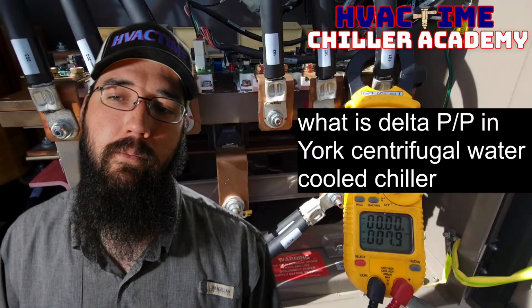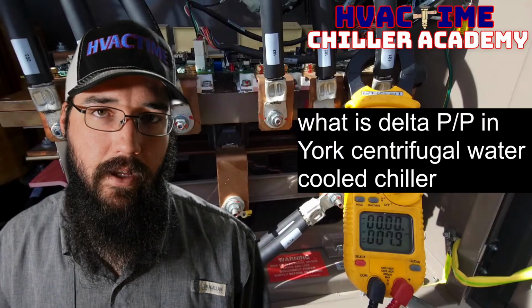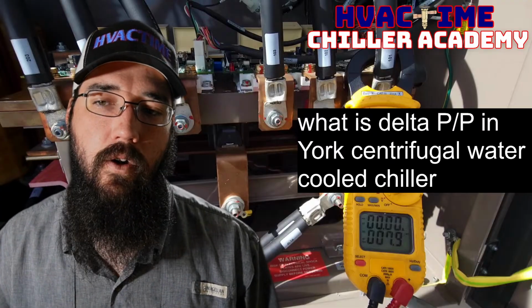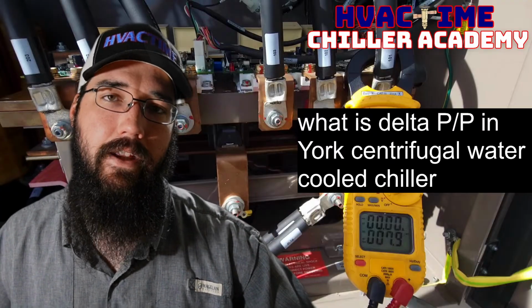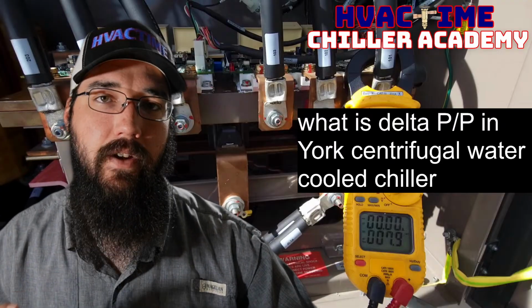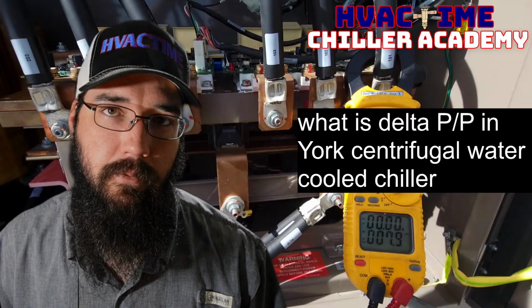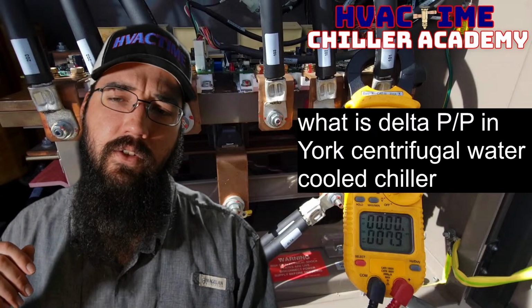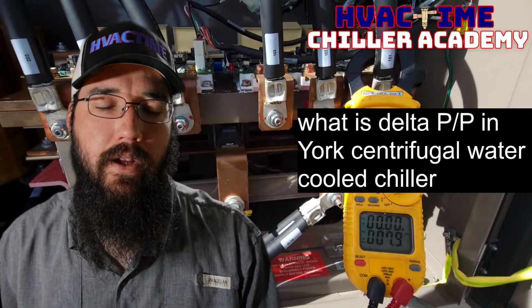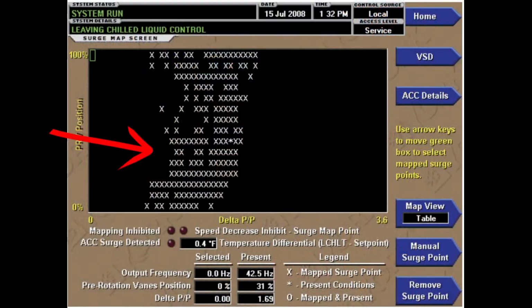I don't remember if York is actually doing that, or if they're just taking the raw gauge condenser pressure and gauge evaporator pressure and dividing them into one another. Either way, that is what it is explaining to you. And what it's used for is to control the surge condition. So we have our delta P over P down here. This is the surge map inside of the compressor screen.